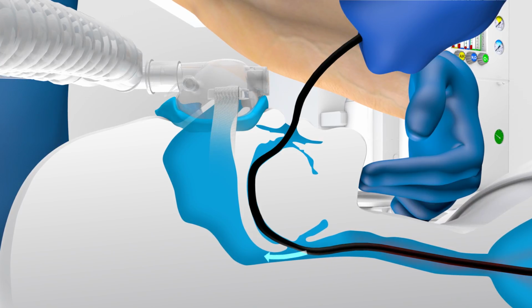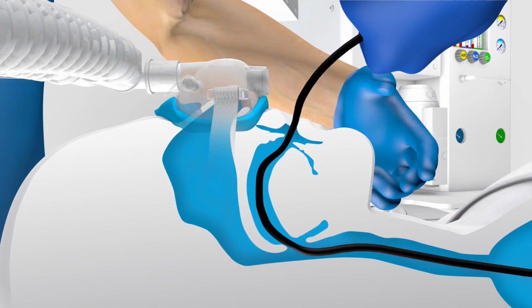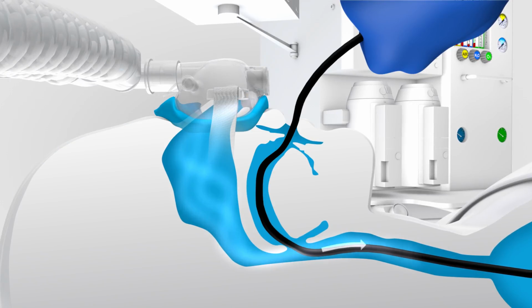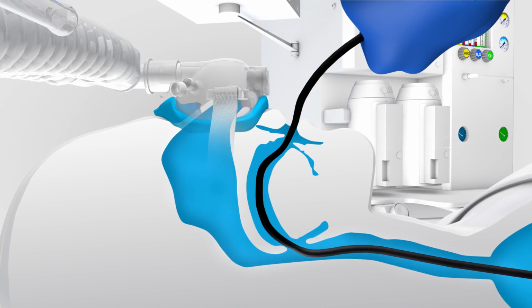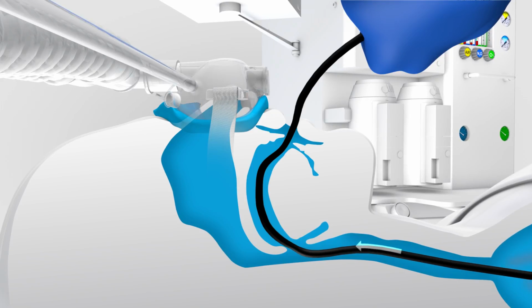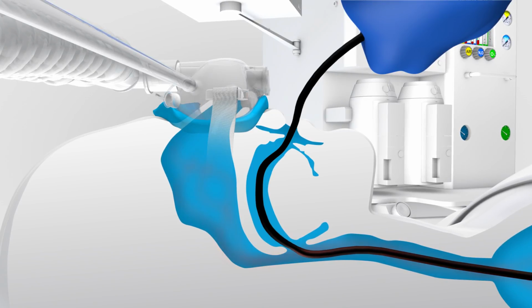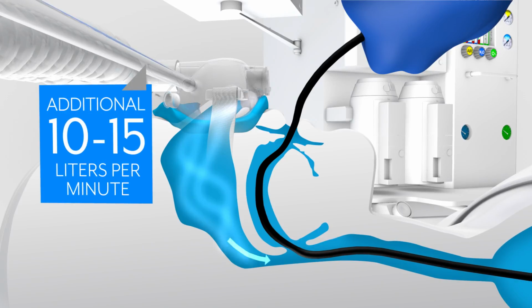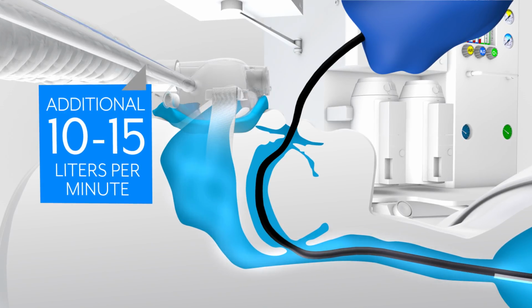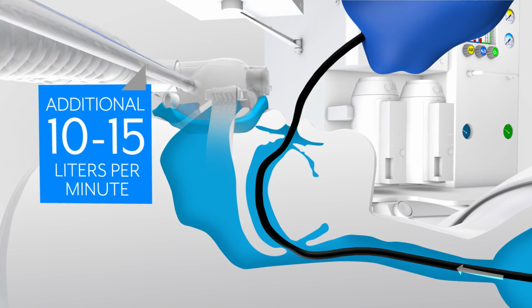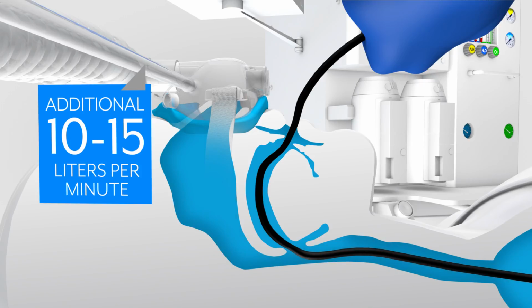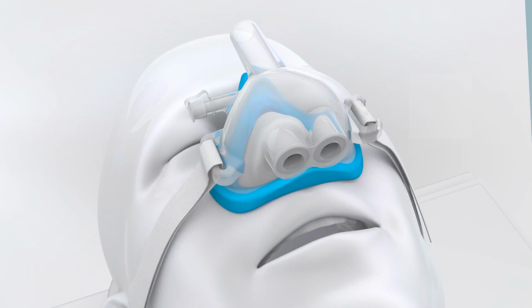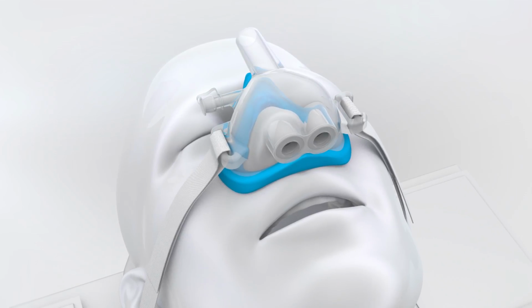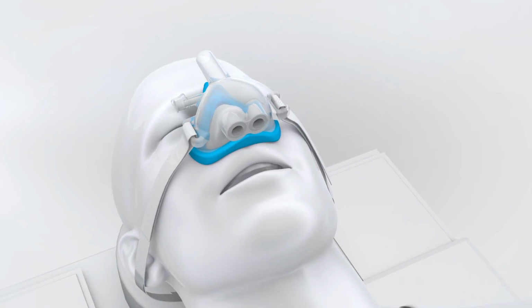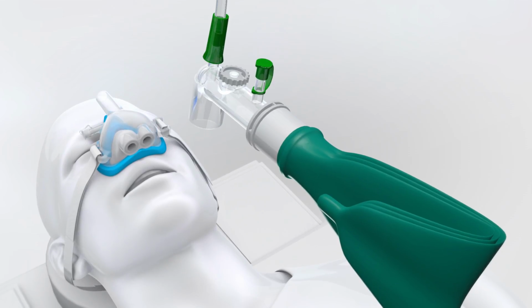During procedures where you expect an excessive leak from the mouth, such as awake fiber optic bronchoscopy, rigid bronchoscopy, and laryngoscopy, attach a second source of oxygen to the supplemental oxygen port using any standard oxygen tubing. The additional 10 to 15 liters per minute supplied from an auxiliary source helps to overcome the mouth leak, and in combination with the flow from the circuit, delivers pressurized high flows of oxygen through the nasopharynx directed towards the glottis. In remote locations where anesthesia machines are absent, the SuperNO2VA device is effective with the use of a hyperinflation bag and supplemental oxygen source.